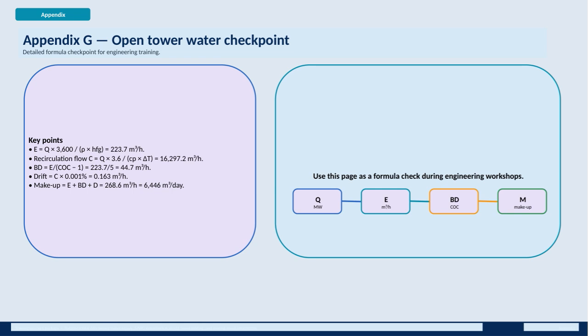Next, the recirculation flow, labeled C, is derived by multiplying Q by 3.6 and divided by the product of specific heat capacity and the temperature difference. The result is approximately 16,297.2 cubic meters per hour, indicating how much water is cycled to the cooling system.